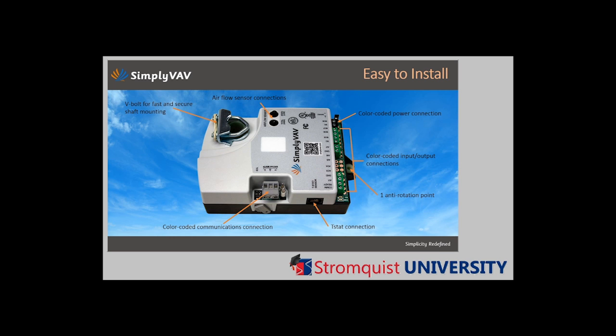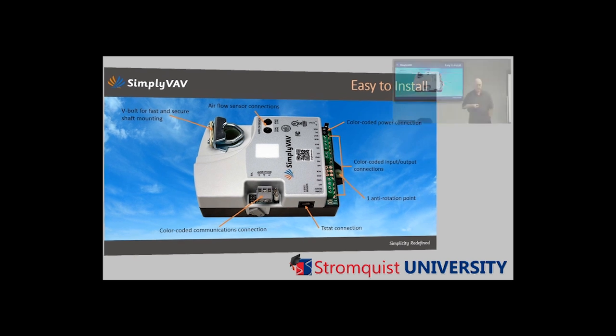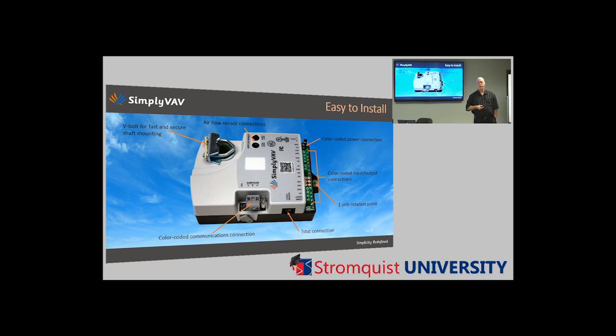An important thing to point out is that no matter which KMC temperature sensor you are using to connect to the Simply VAV product, it is all done with a standard Ethernet cable. It's not a crossover cable, it's not a patch cable, it's not a specialty cable that's going to drive your cost for the job up. It's a standard Ethernet cable. You can go purchase it at any electronic supply house, Best Buy, or electronic supplier of your choice.